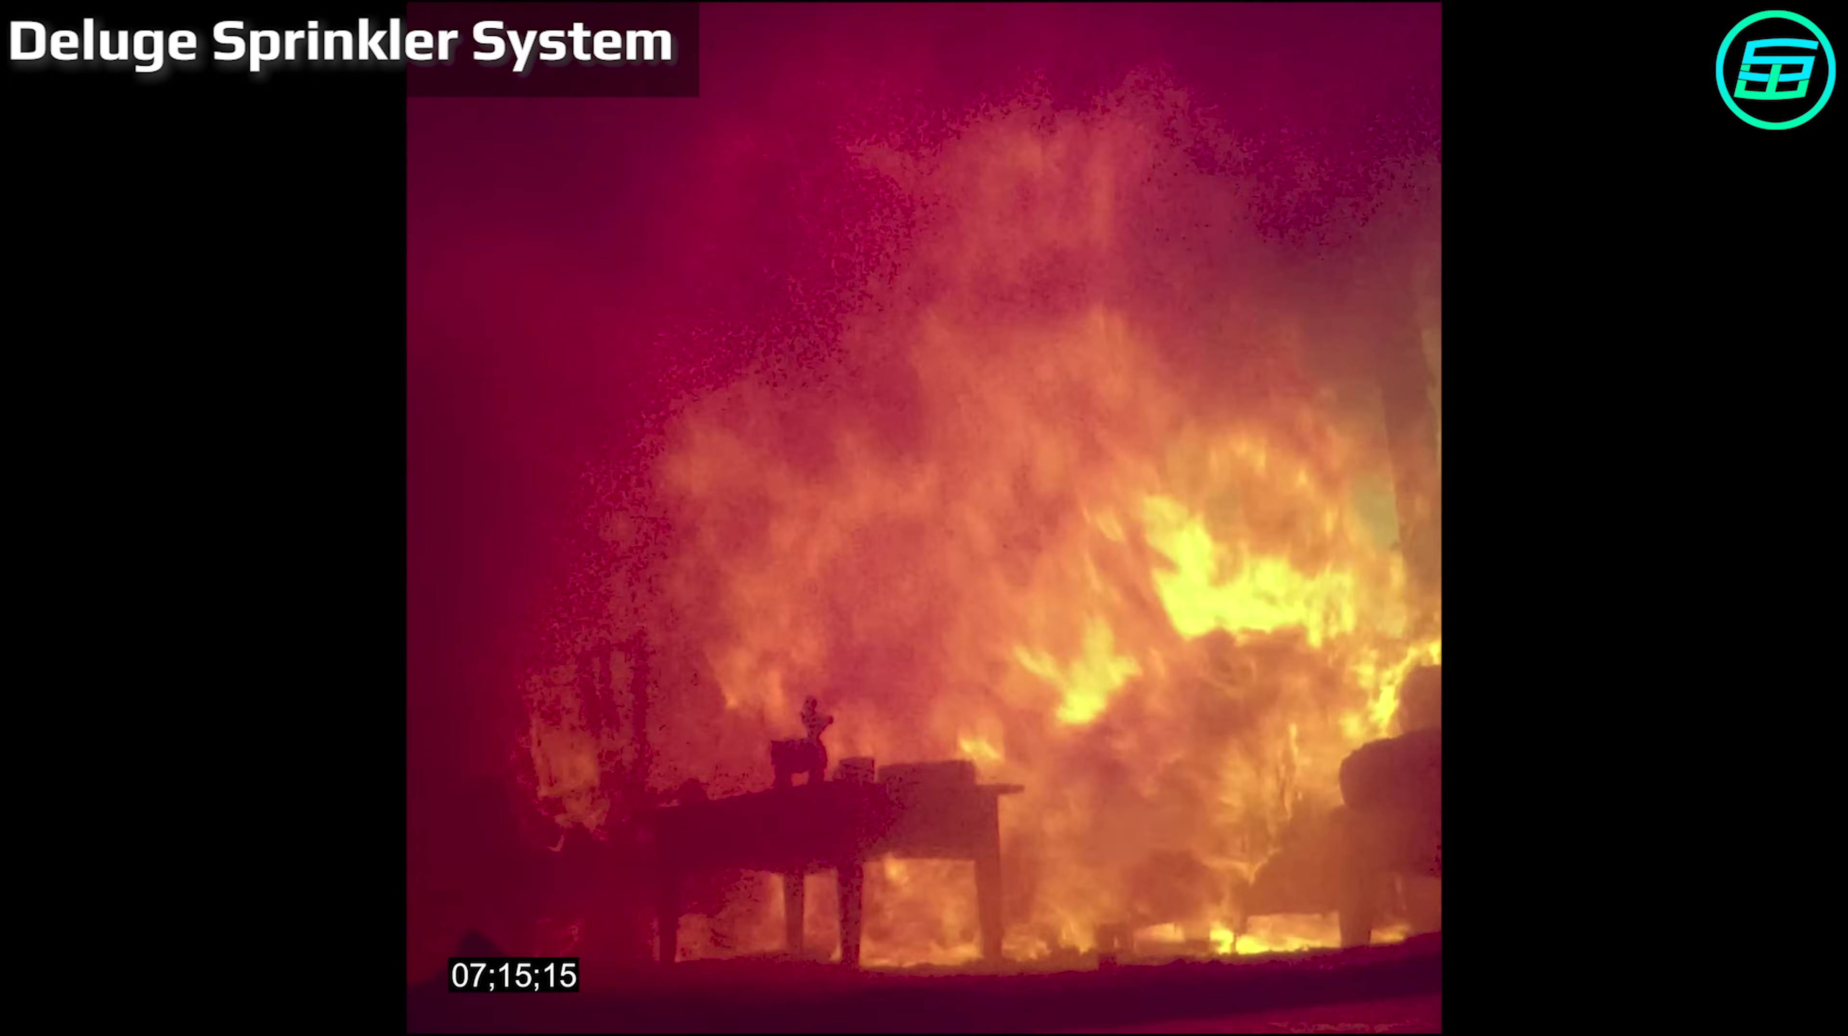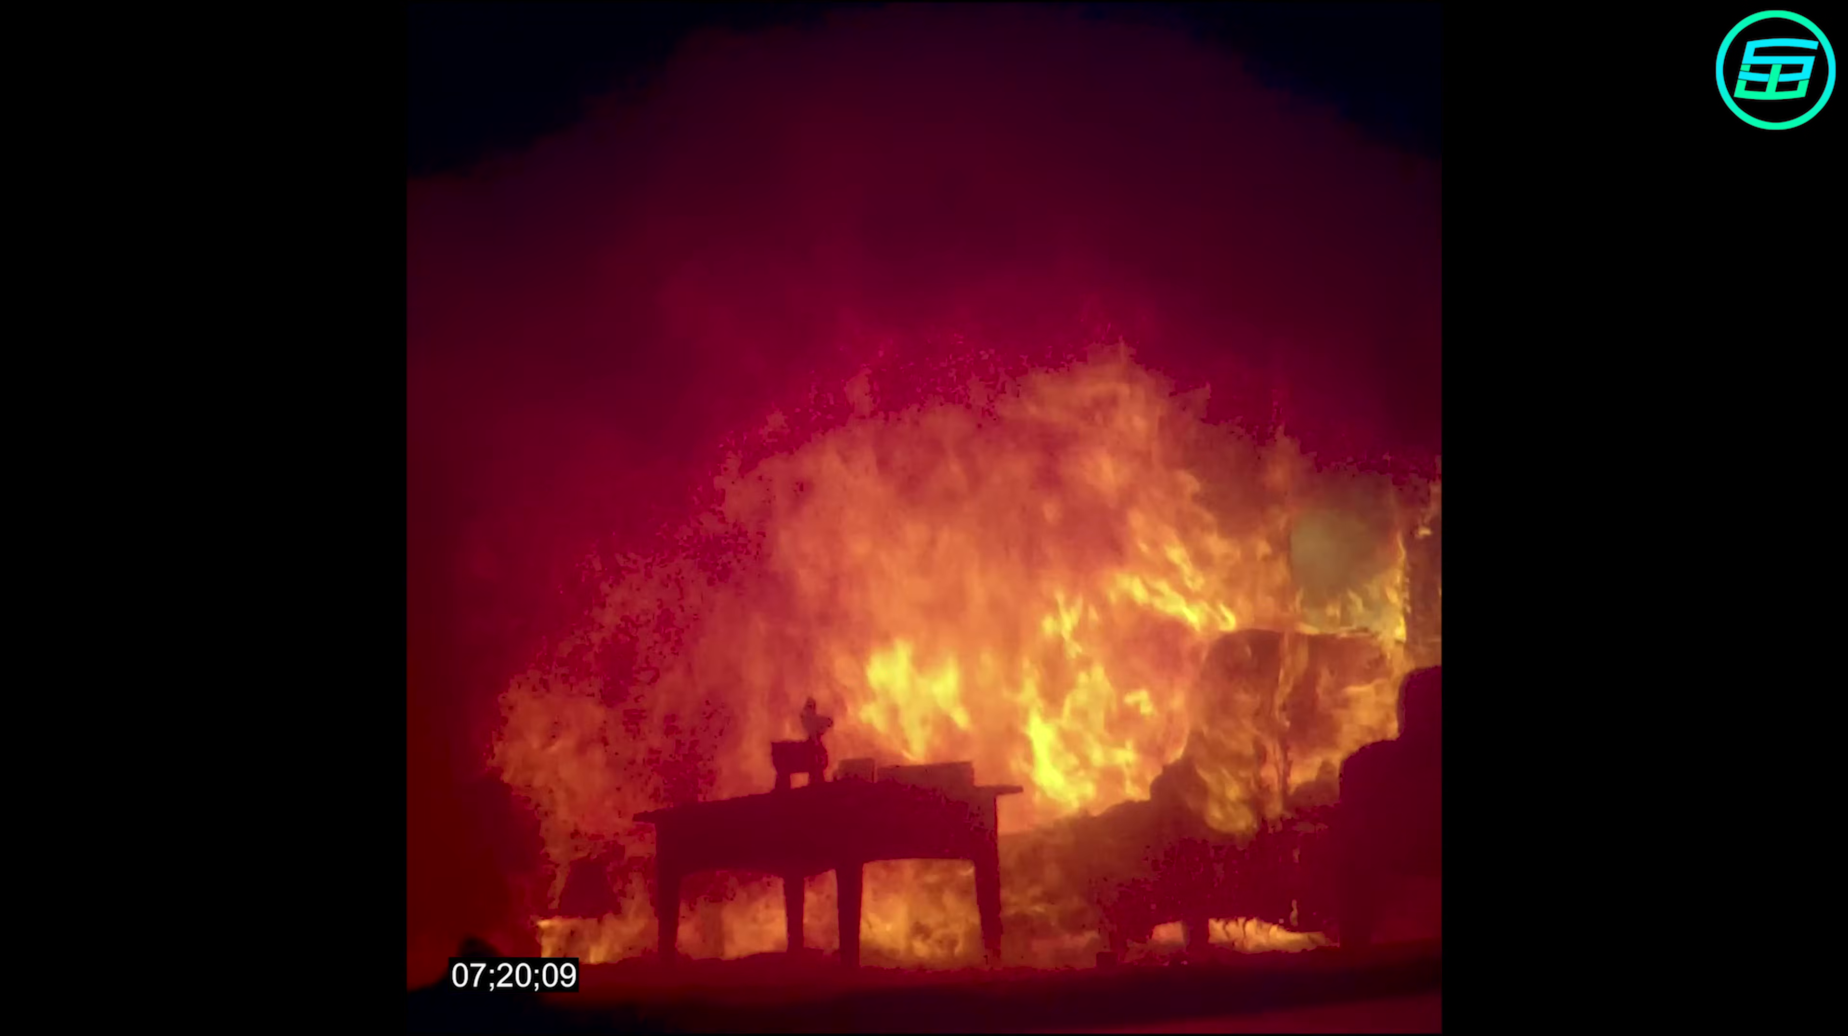Once heat is detected, water fills the pipes and is released to all open sprinkler heads, creating a flooding effect across the entire area. This system is most often used in industries with flammable liquids, which pose the threat of rapidly spreading fires.